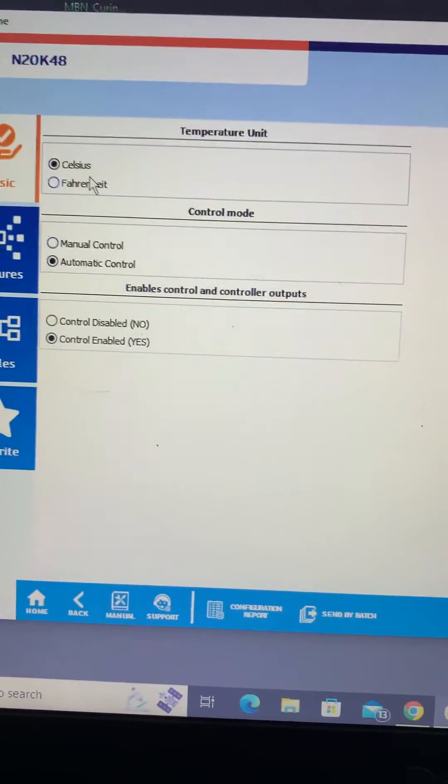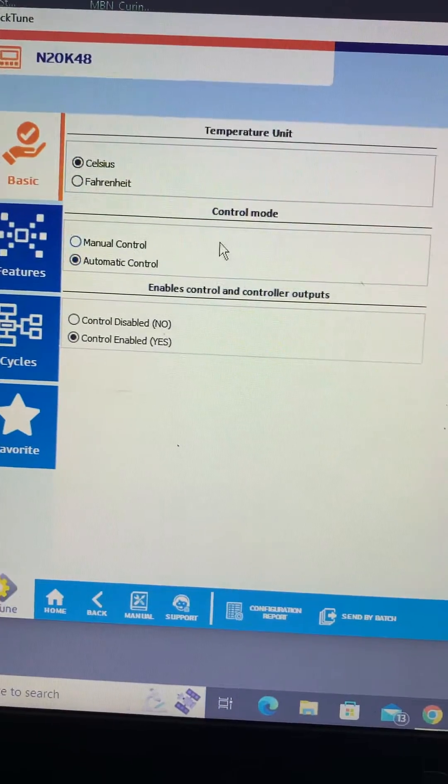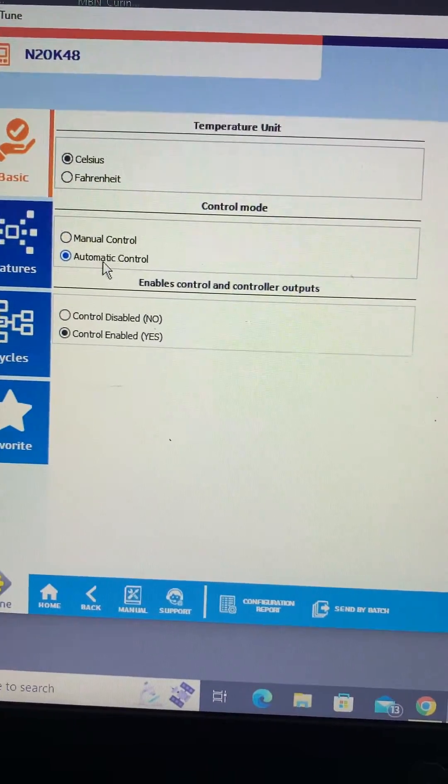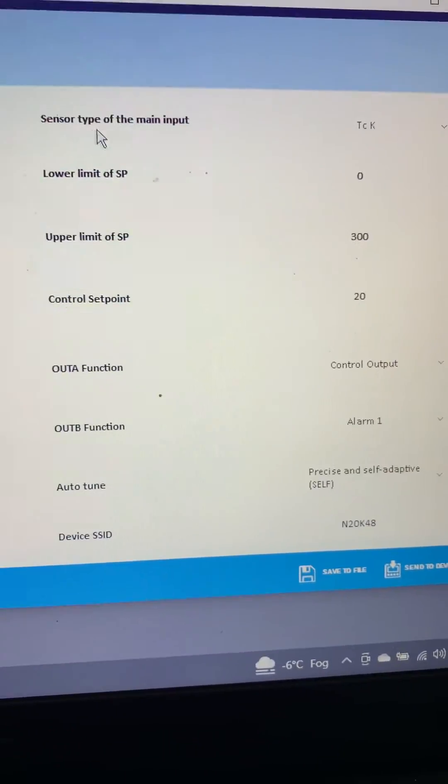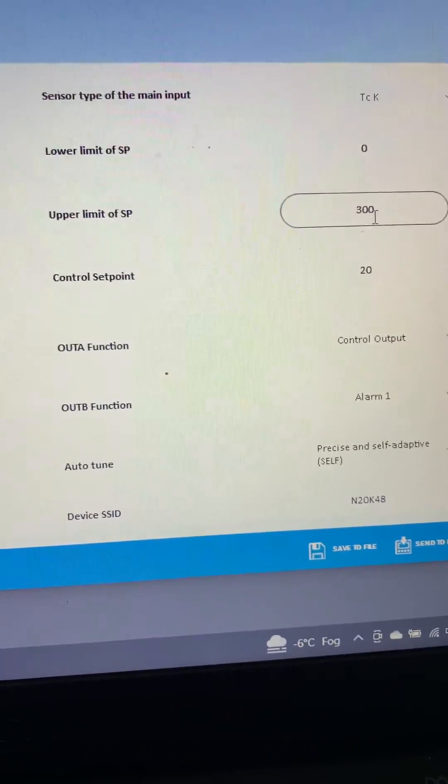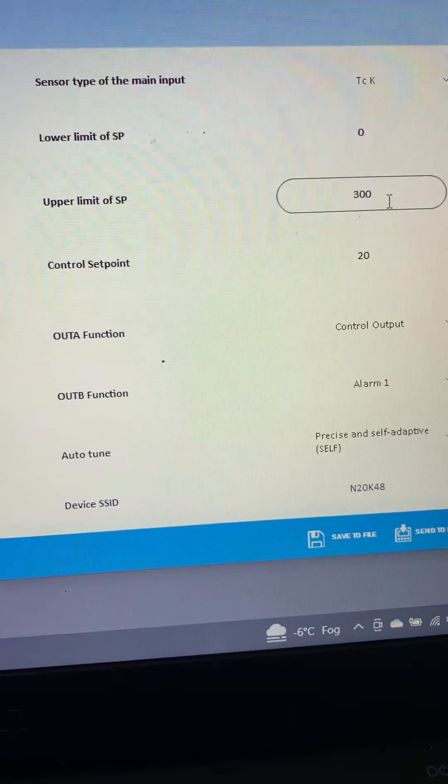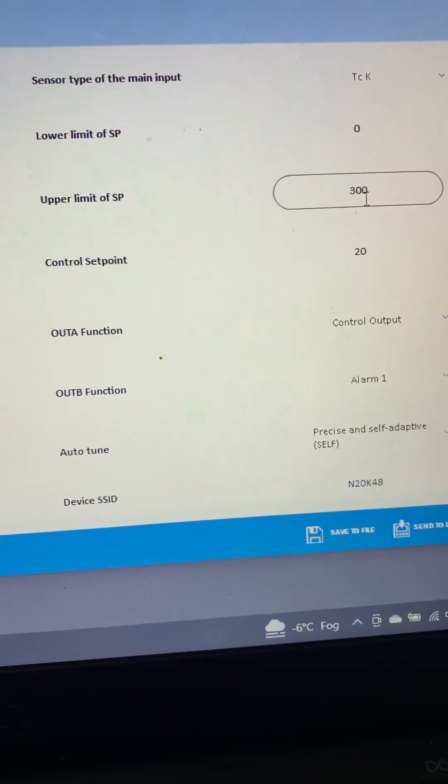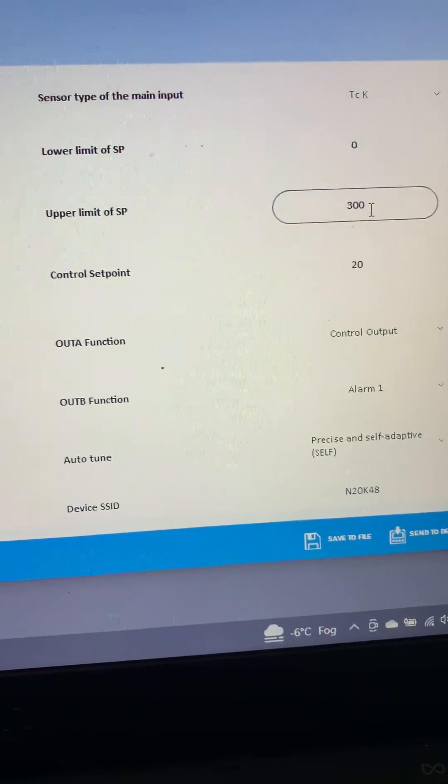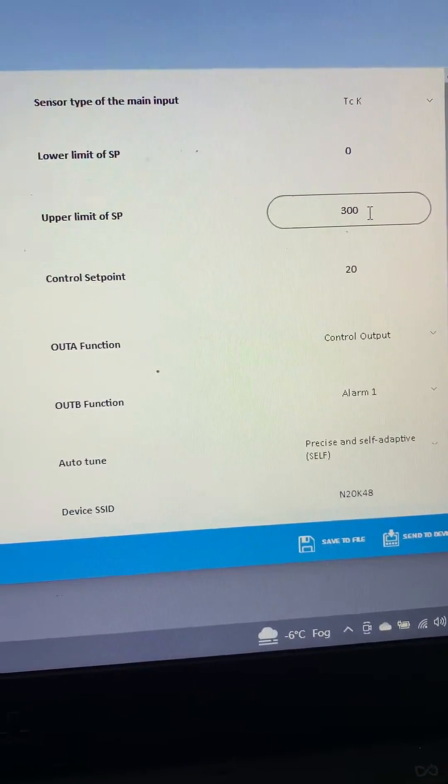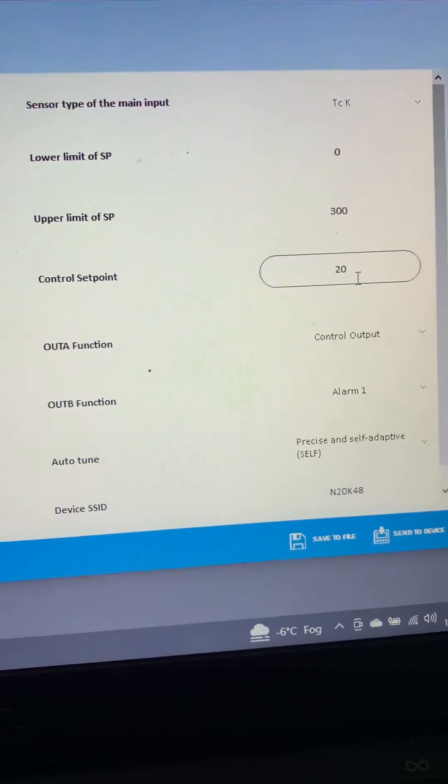Going through a few of the basic settings: temperature unit, yes, Celsius. Control mode by default is manual, we always want automatic and enabling the control, yes. Sensor type, we've gone for a type K here. We know for this particular process it looks like about 250 max, so we've capped the set point at 300, which is always a pretty good idea to stop people putting in silly values.